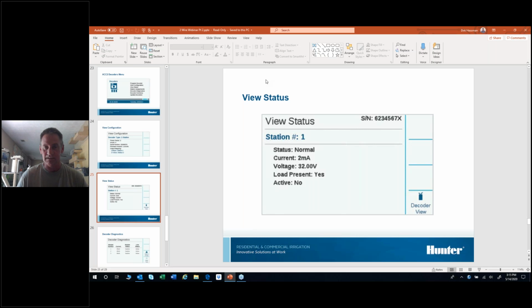Current on this one is 2 milliamps, which is good for a decoder just sitting there dormant—typically it's around 3, so 2 to 3 is good. Load present means there's a solenoid hooked up to it, and active shows whether it's on or not—this one's not.